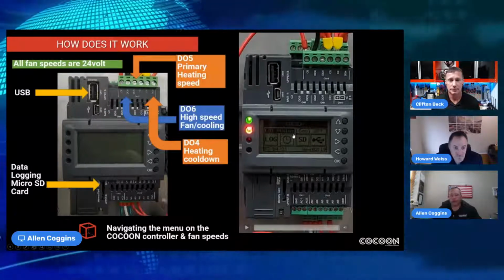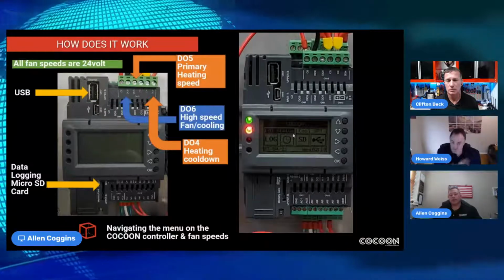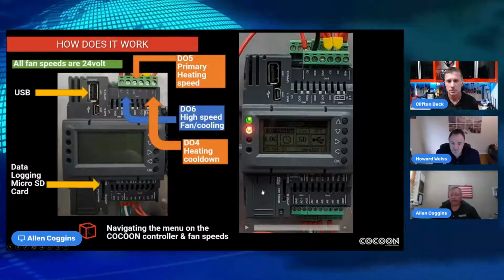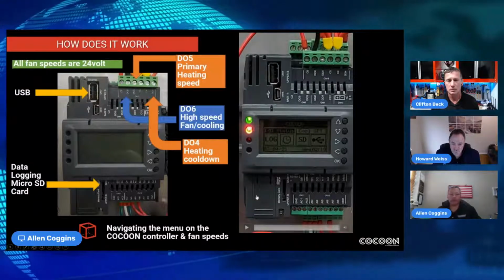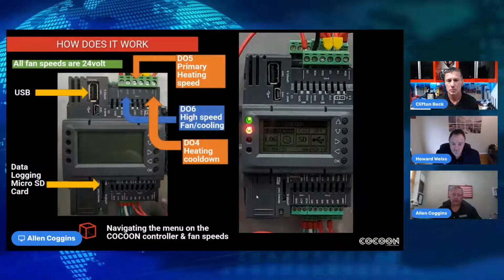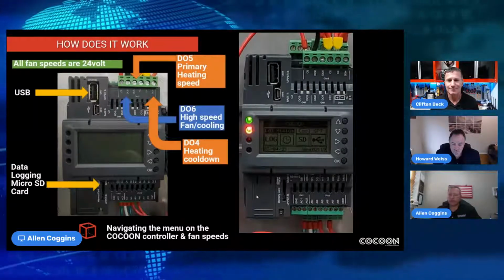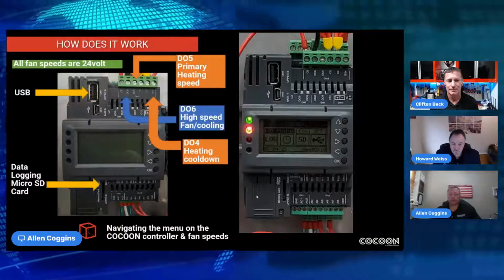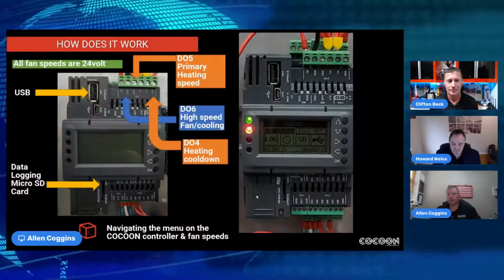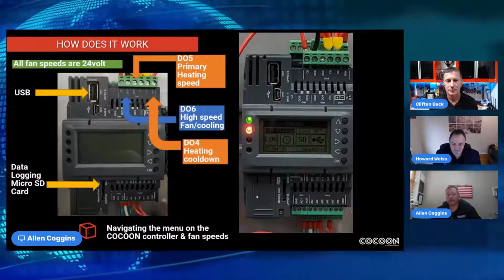Thank you. With your IO statuses, your input output, what's happening? Do we have a call for heat? Is the fan on? Is the fan proving switch on? Those things you'd normally pull out your meter to check, you can now check right through the controller.